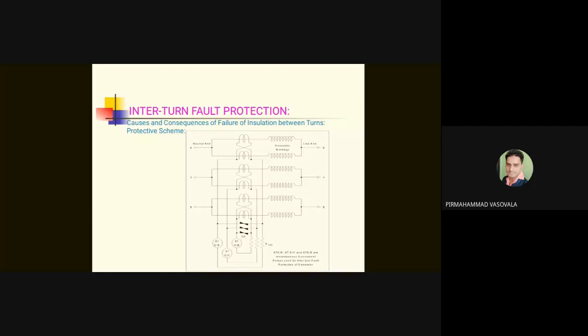An inter-turn fault itself is not a very damaging or dangerous fault, because it does not generate very large current. So it is not a problem of any big overheating, but there will be local heating wherever there is a fault. Fault means there will be a small arc, and arcing causes local heating, which will finally result in a line to line or line to ground fault. Therefore we don't wait for a line to line or line to ground fault, but act when the inter-turn fault occurs. This is also a fault within the generator, and therefore it is class A protection. Relays used are instantaneous overcurrent relays once again.